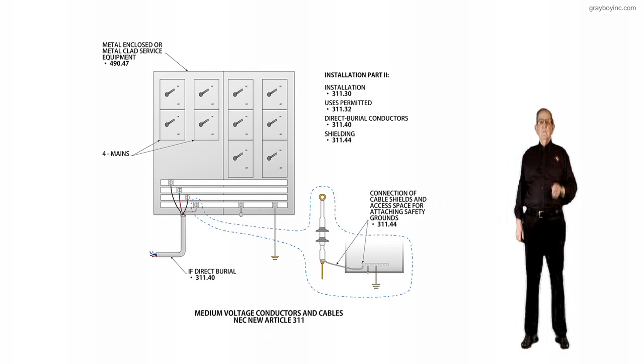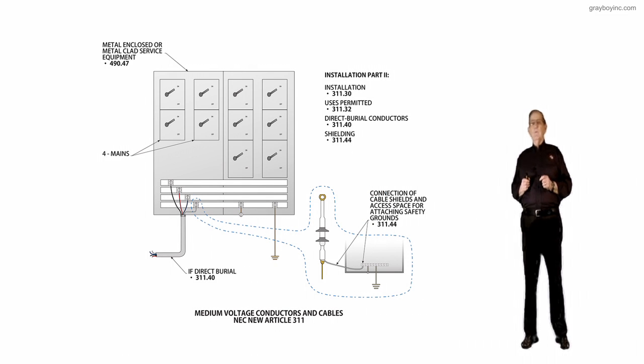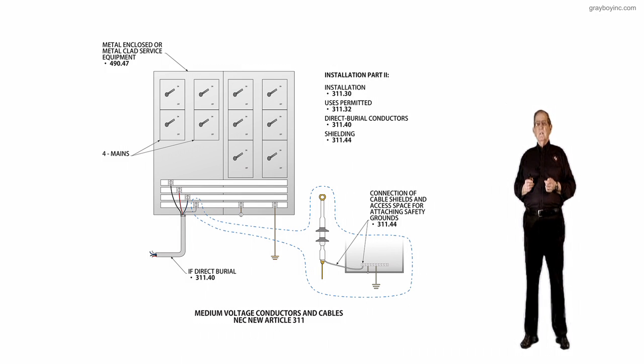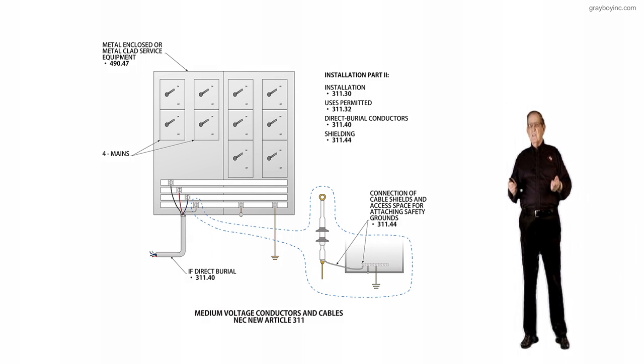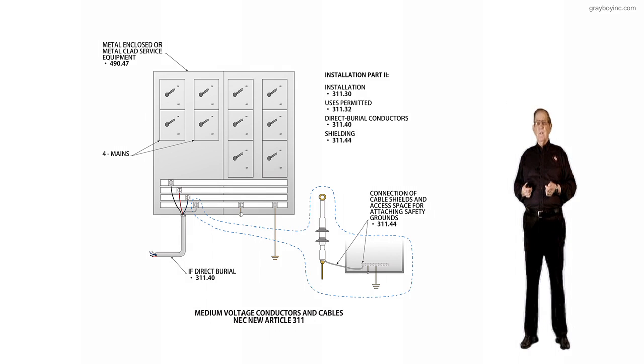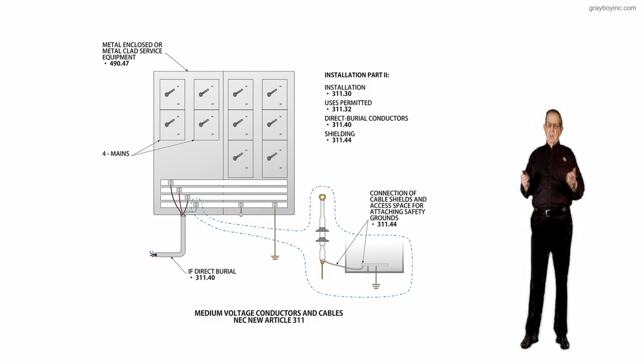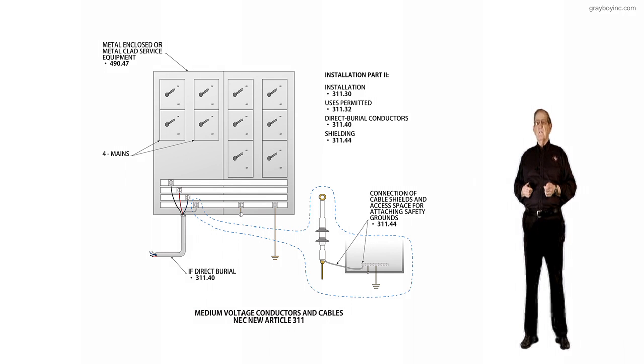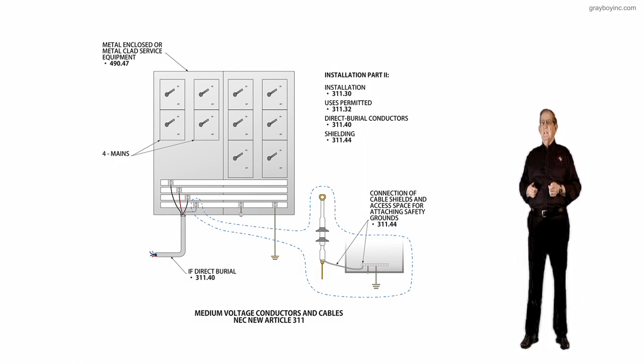This illustration deals with medium voltage conductors and cables in accordance with NEC new Article 311, and of course we're dealing with Part 2 there. The purpose of the change: a new article is added to address medium voltage conductors and cables. This new Article 311, Part 2, covers installations, uses permitted, direct buried conductors, support, and shielding rules. This new article was formed from existing Article 310 and 328 in the 2017 NEC.